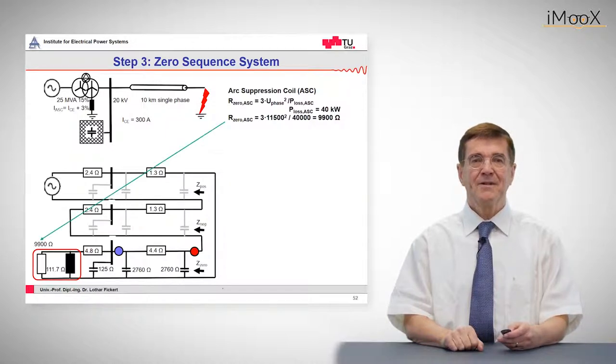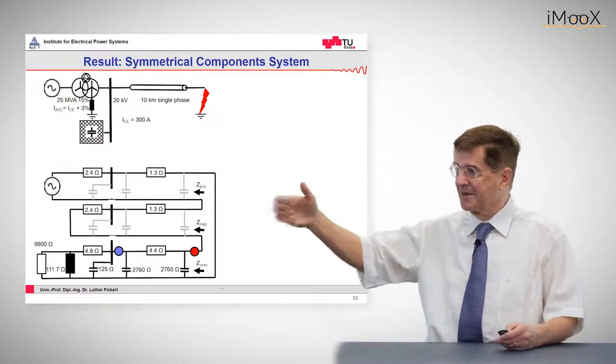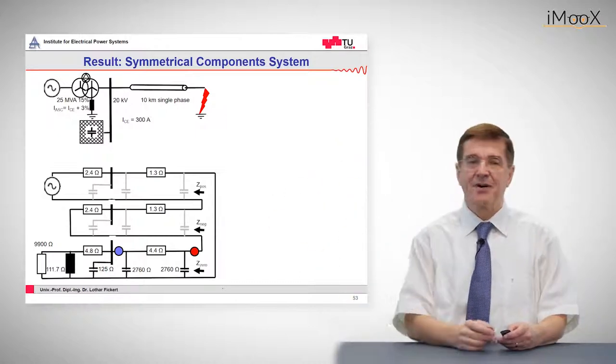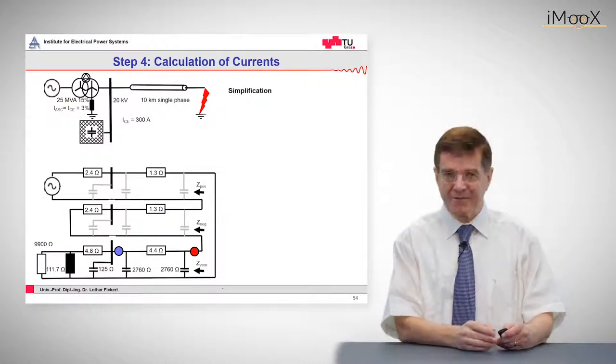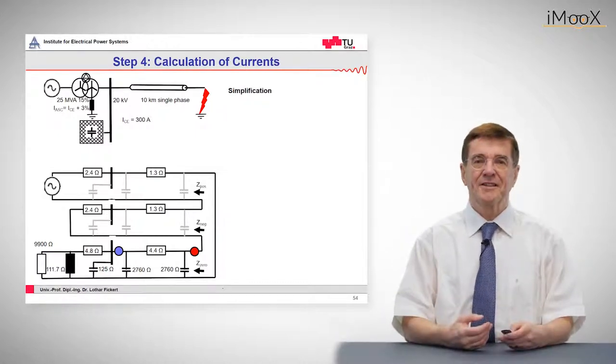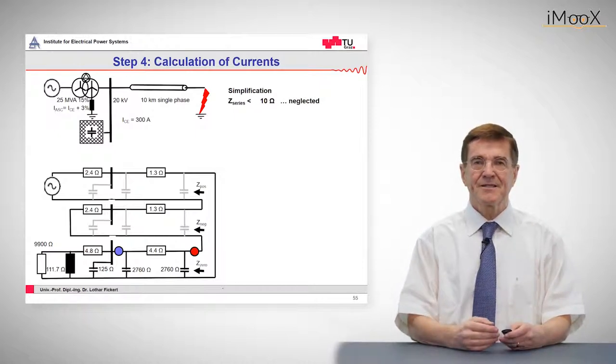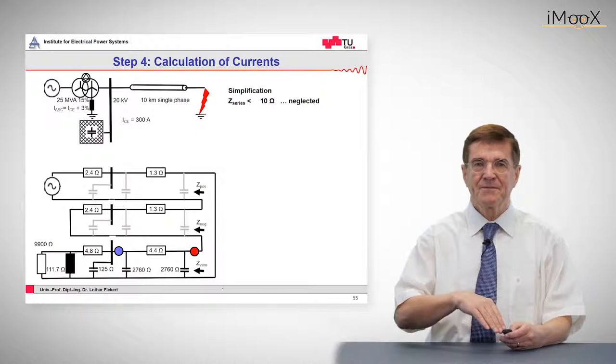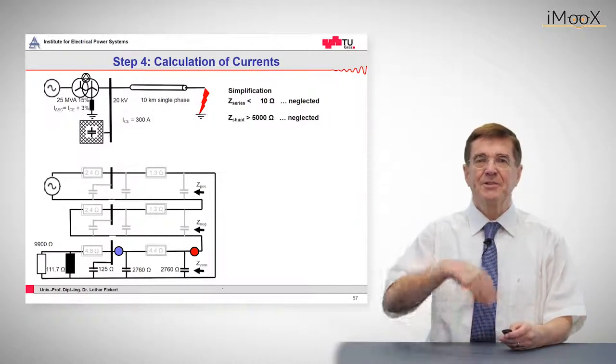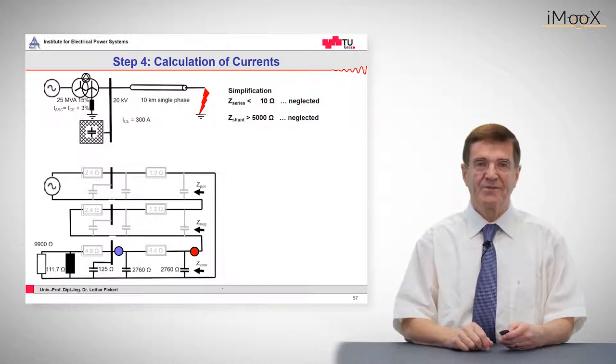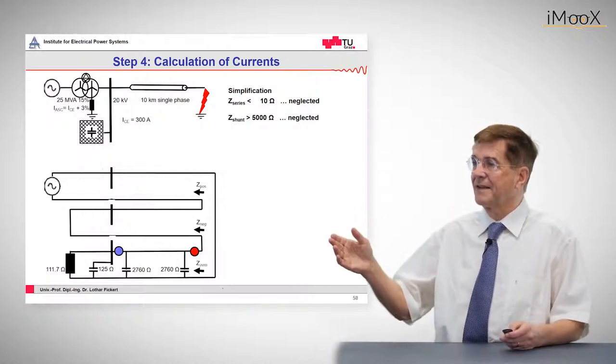Now we have the full picture as you see: the positive sequence, negative sequence, zero sequence, and now we go into the calculation. First I want to simplify with you the calculation, and that means we omit all series reactances which are below 5 ohms or 10 ohms, and also the shunt impedances which are above 5000 ohms. All these are neglected. I indicate this in gray and then I take them just out.